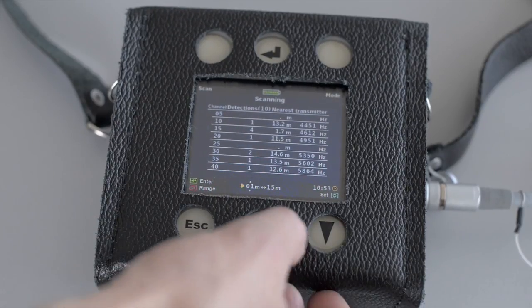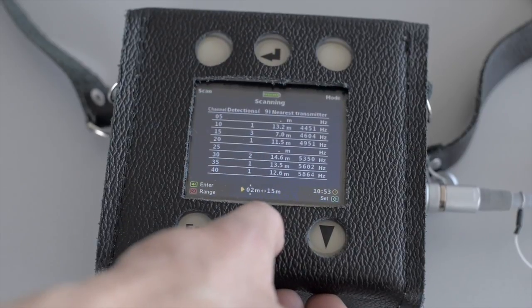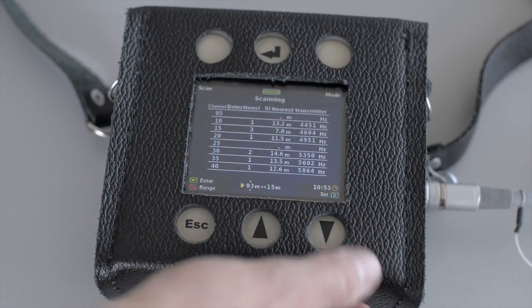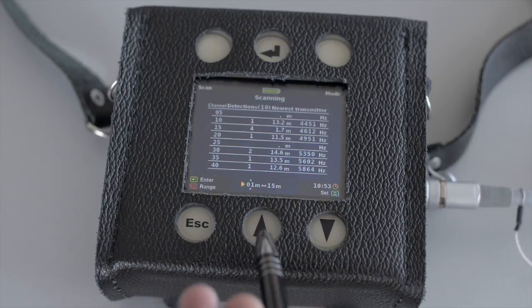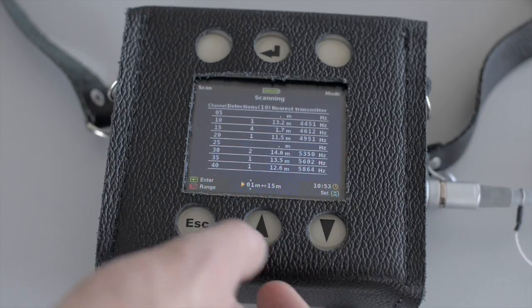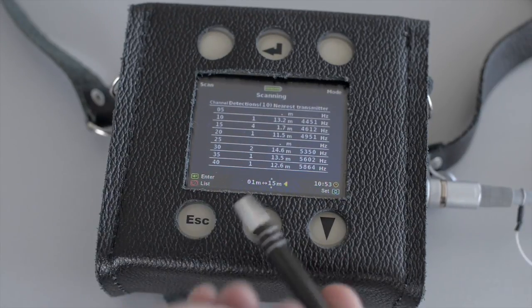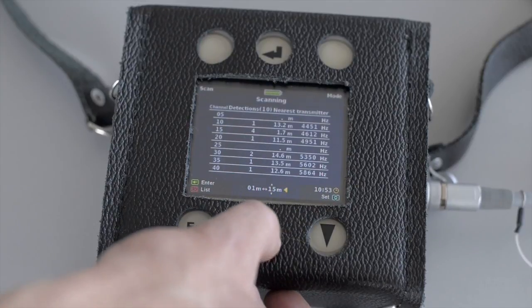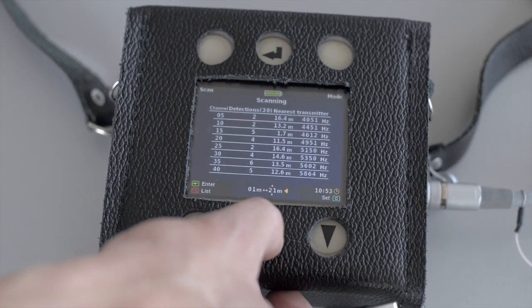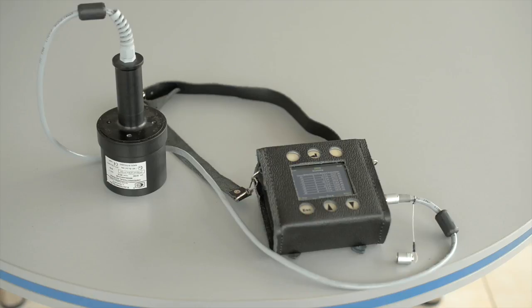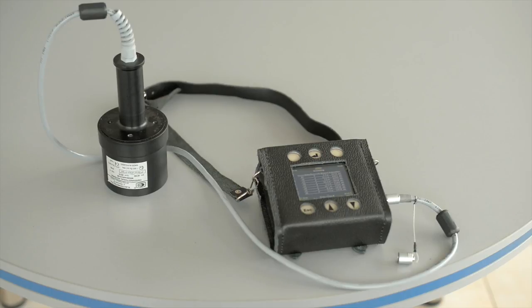Now use the arrow down and arrow up keys to set the desired start range in meters. Once set, press the Escape key again and use the arrow up and arrow down keys to set the end scan range in meters. Now you are ready to proceed with the scan. To do that, press the scan key in the top left corner of the central unit.